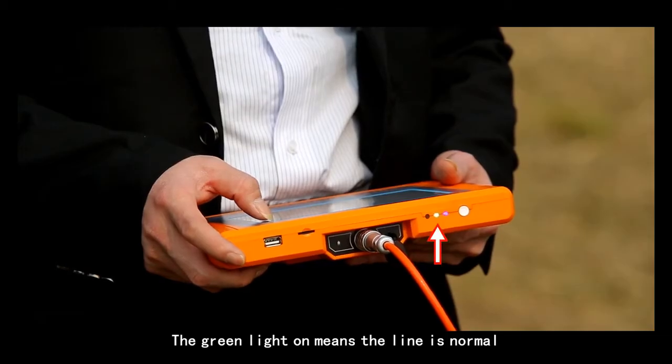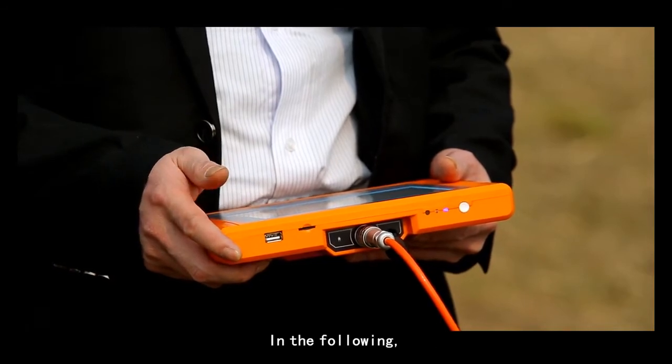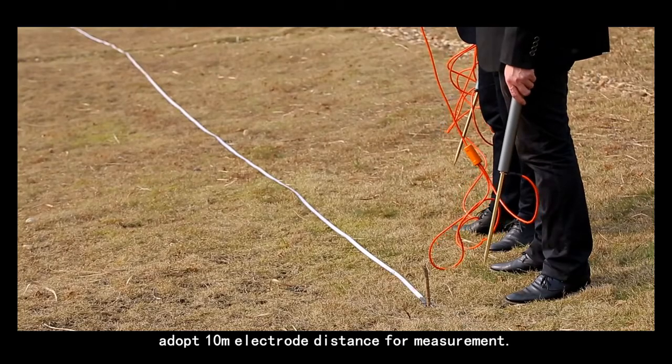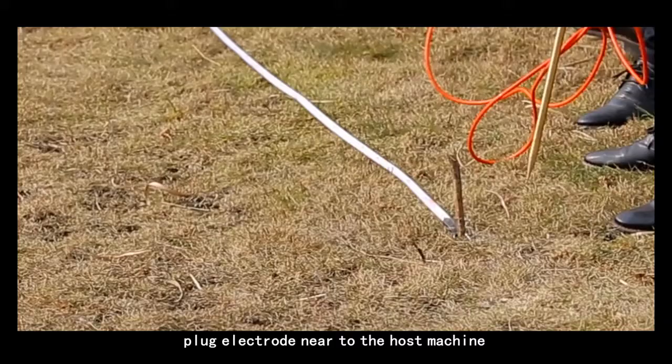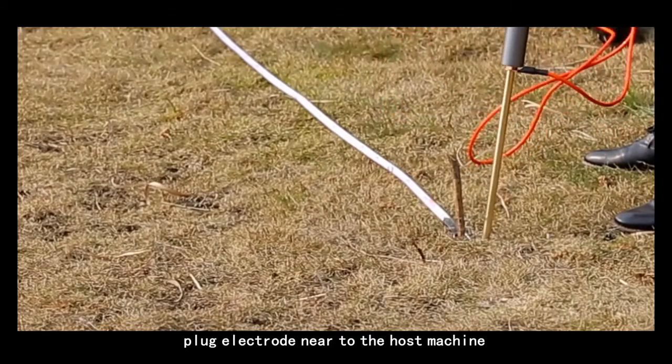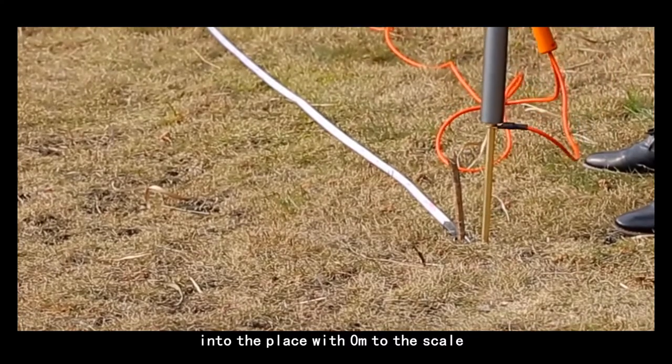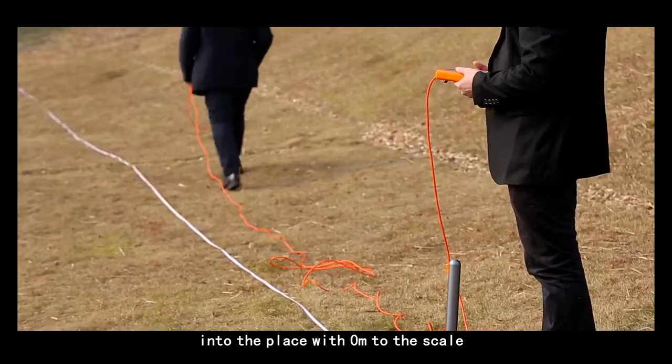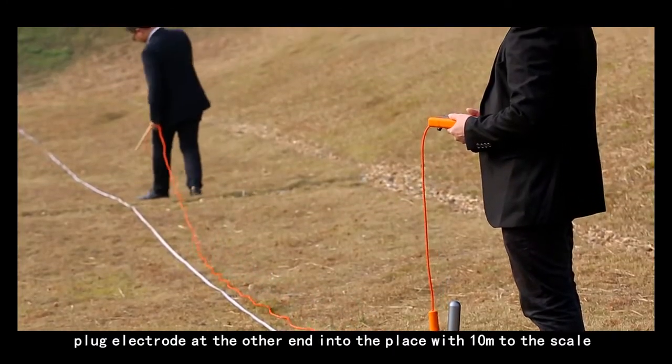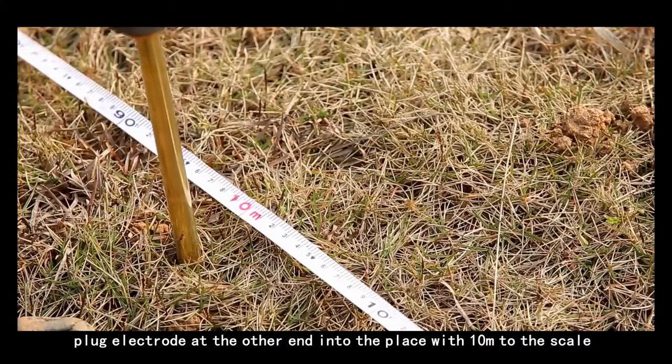In the following, adopt 10 meters electrode distance for measurement. Plug electrode near to the host machine into the place with 0 meters to the scale. Plug electrode at the other end into the place with 10 meters to the scale.